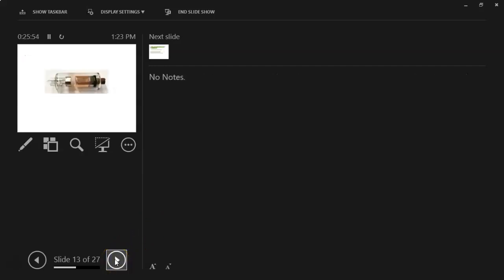So here's a blurry picture. I wish that was a little sharper. I'll have to get maybe a different picture. You can tell, because you probably know the color of copper, it doesn't take a lot to realize that this is the anode side, because this is the copper stem. And you can't really see it, but embedded in the end here would be the tungsten target. And over here is the cathode side, and you can see it's incredibly short. It's only separated by like an inch or something. It's a very, very short distance that the electrons go from one side to the other.